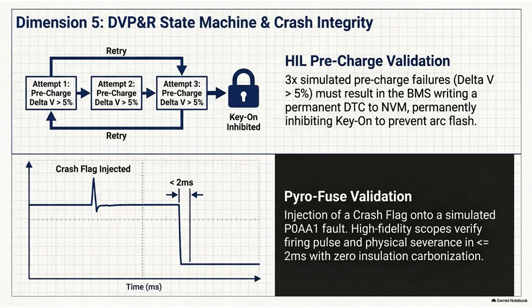They have to mathematically prove that the BMS software instantly recognizes the injected crash flag, immediately overrides all other pending software protocols, sends a massive firing voltage pulse to the Pyro-fuse squib, and that the chemical explosive charge detonates and physically blows the thick copper circuit entirely apart. And the timeline they are obsessively looking for on the graph is that critical 2-millisecond window you mentioned earlier. The oscilloscope traces must definitively show the massive current dropping from thousands of amps to absolute zero in less than 2 milliseconds.